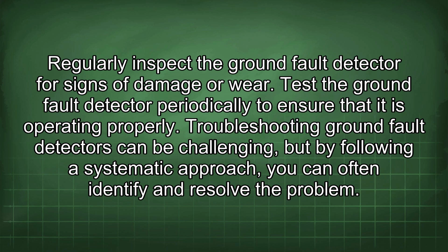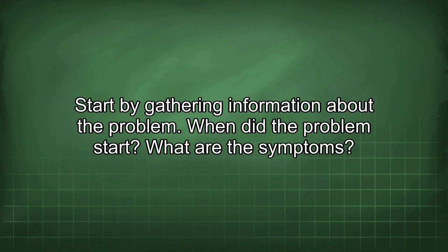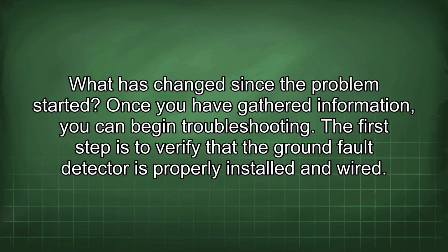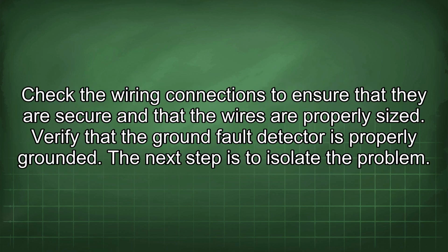Troubleshooting ground fault detectors can be challenging, but by following a systematic approach, you can often identify and resolve the problem. Start by gathering information about the problem. When did the problem start? What are the symptoms? What has changed since the problem started? Once you have gathered information, you can begin troubleshooting. The first step is to verify that the ground fault detector is properly installed and wired. Check the wiring connections to ensure that they are secure and that the wires are properly sized. Verify that the ground fault detector is properly grounded.